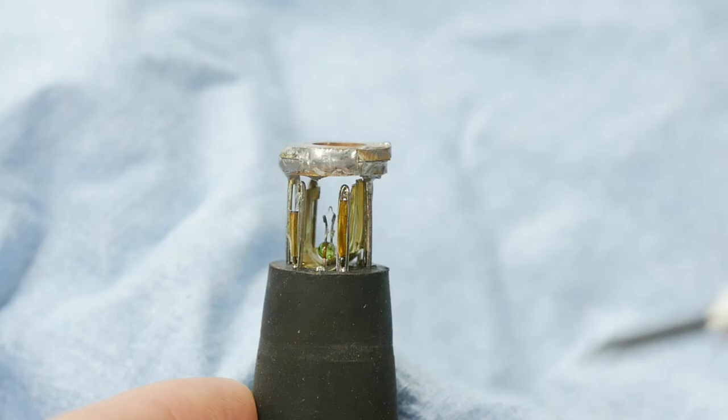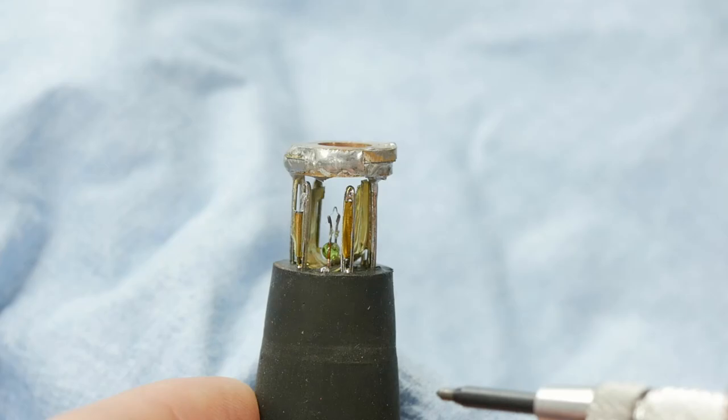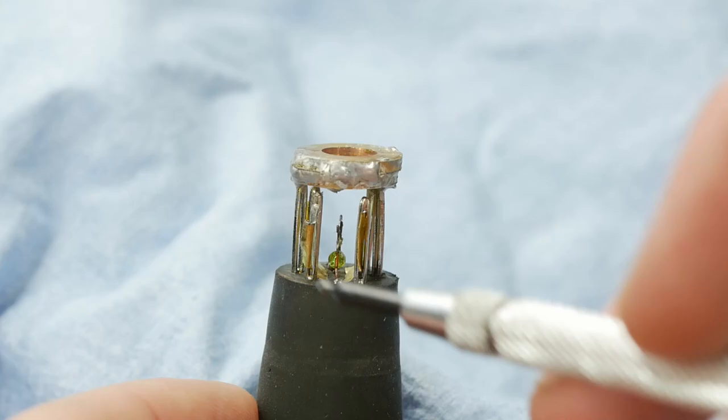Let it dry either by passing current through the filament or just blowing hot air on it or just waiting around. Eventually what we'll have is a filament coated with the powder. It's a way of getting the powder onto the filament. Then we put this thing together into the mass spectrometer and turn it on and heat it up. When the filament gets to red heat, it will actually ionize the sample for us. It's a process that happens all by itself. Tungsten filaments can boil off electrons when it gets hot. It can also produce ions.